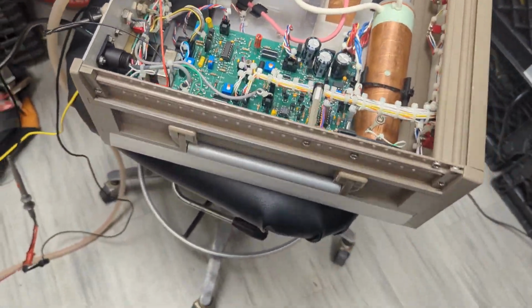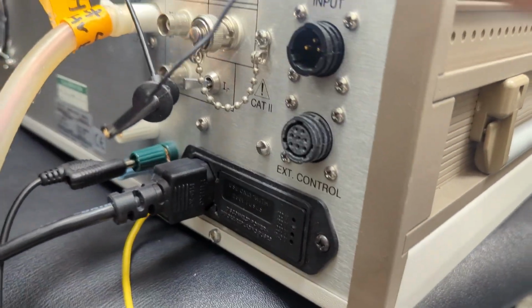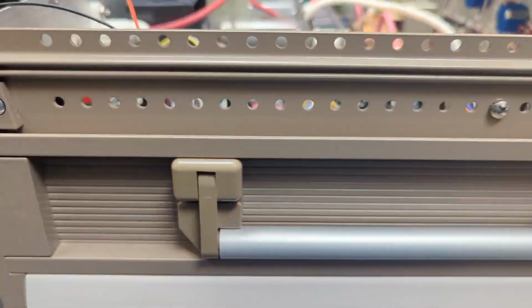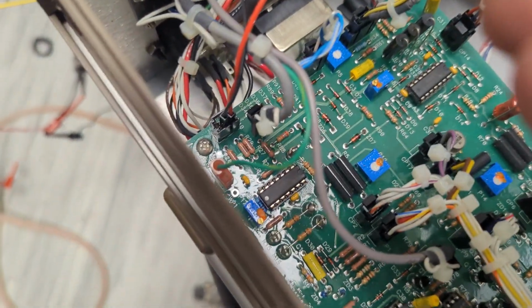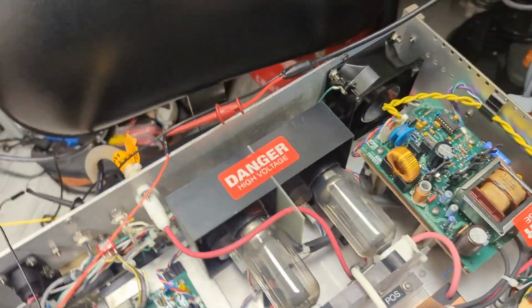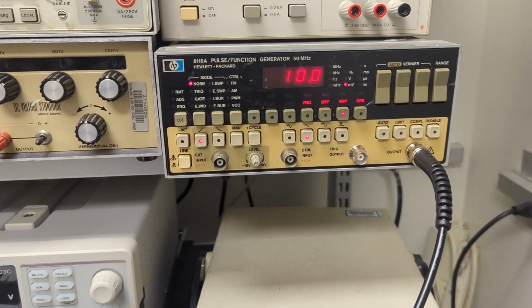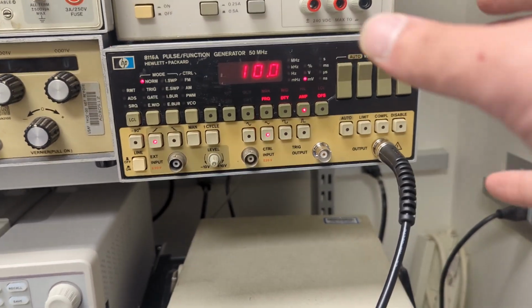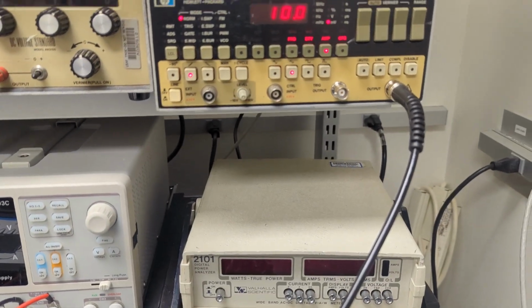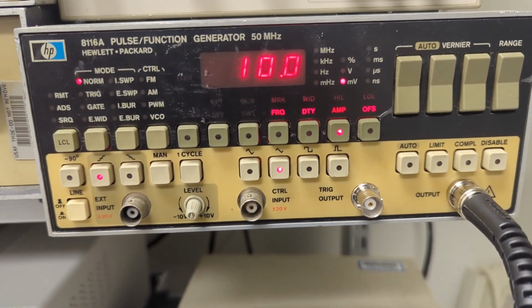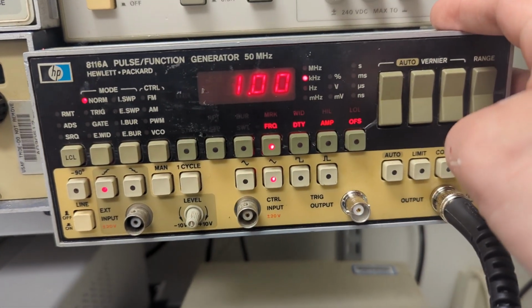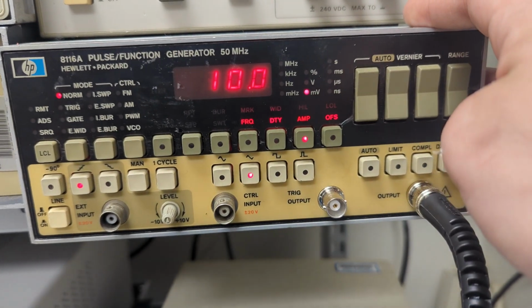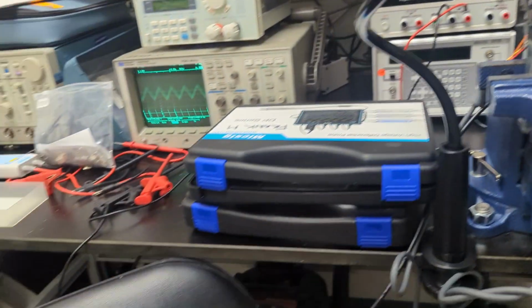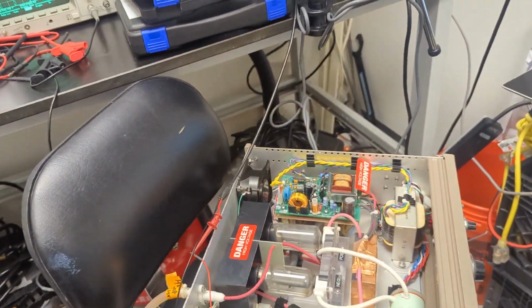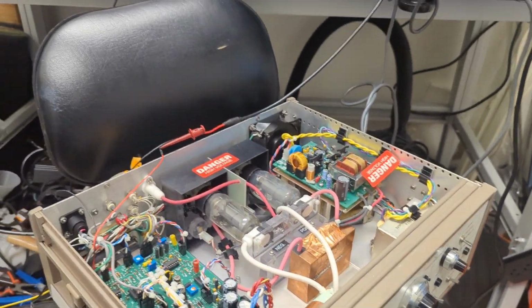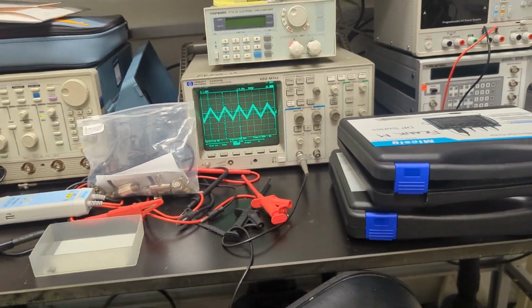All right, so we're gonna test the amplifier. I had to take the top panel off, because the amplifier input is this 3-pronged input. I don't have anything like that to hook up to, so I'm connecting straight to the board right there. I am using this HP 8116A pulse generator. I've got the amplitude set to 10 millivolts. I thought it'd be cool to try to amplify a much lower voltage. We're at a frequency of just 1 kilohertz, and it's a triangle wave. Amplitude is 10 millivolts, and we are at the 100 volt per volt amplification setting.